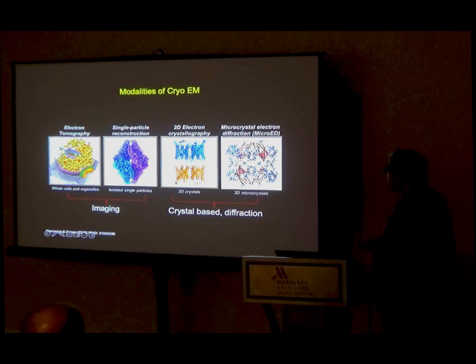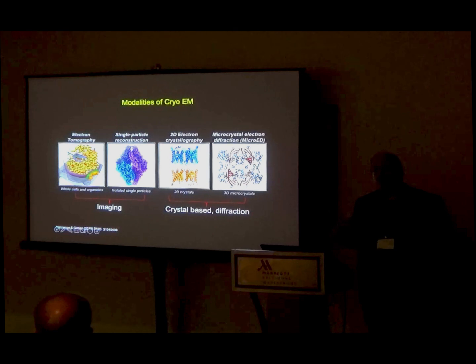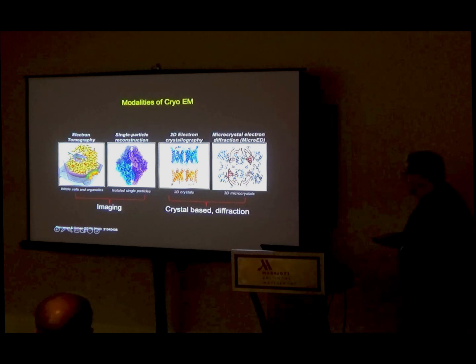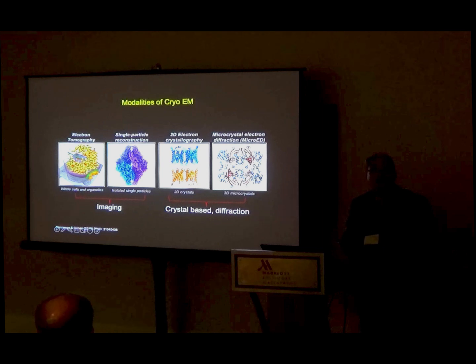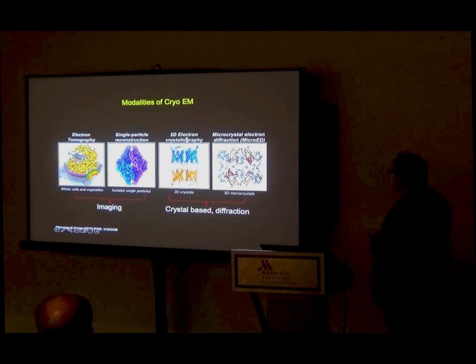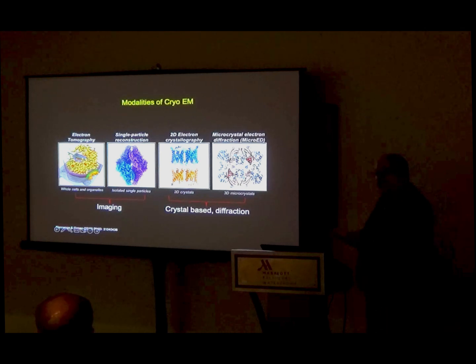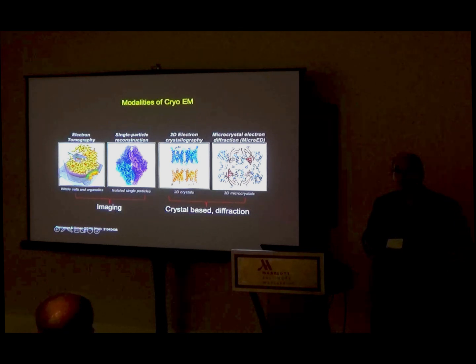The reason I like to start with this slide is to illustrate that all these methods use the same electron microscopes and the same cameras. The only difference is the way in which you run the electron microscope. Here you have the imaging modalities — tomography and single particle reconstructions — where you use the microscope in imaging mode and collect pictures at high magnification. In electron crystallography of 2D crystals and microcrystal electron diffraction, which are crystal-based, you can also operate the microscope in diffraction mode and collect diffraction data.